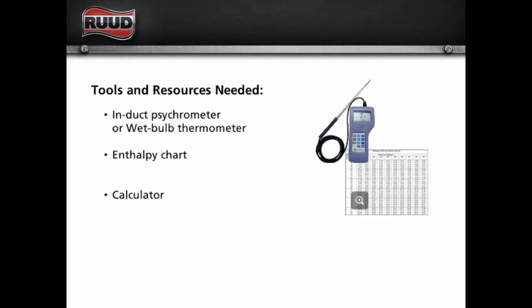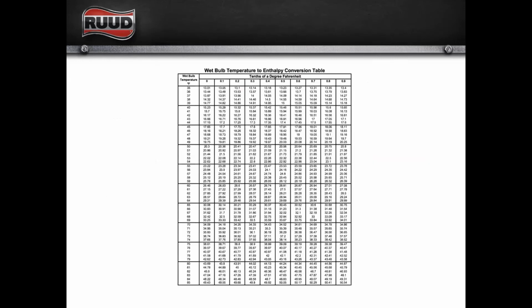So what do we need to do that? We need an induct psychrometer or an induct wet bulb thermometer. And we need an enthalpy chart. And we also need a manometer or a magnehelic gauge so that we can calculate actual cubic feet per minute that we're moving through our duct. We need the chart, which I said I'm going to email out when we're done. And then we also need a calculator, which is really not a problem anymore because we all have one on our phone, right?